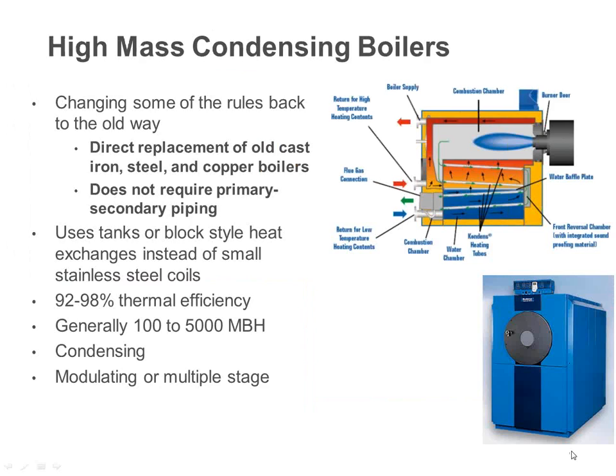The other type of boiler out there is a high mass condensing boiler. We're not real tricky in the hydronic industry. High mass means it holds a lot of water. All right. So basically, it does throw out some of the rules we said earlier. Since I've got this big mass, piping is not as critical because I've got all this water to move around. I'm not talking 25, 30 gallons here. I'm talking on these type of boilers, 2, 3, 4, 500 gallons. So it's almost a built-in buffer tank, but basically it is a high efficiency boiler, high mass.